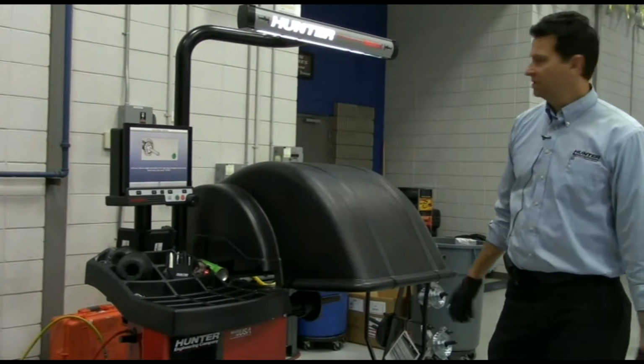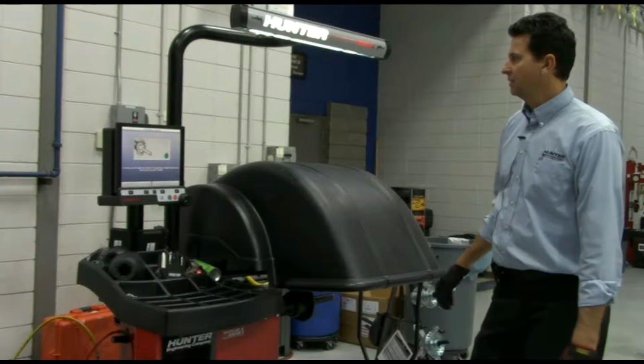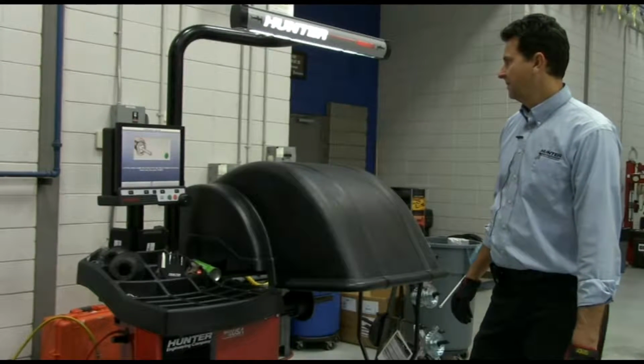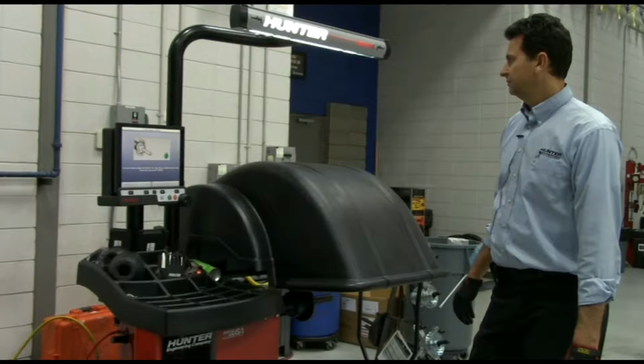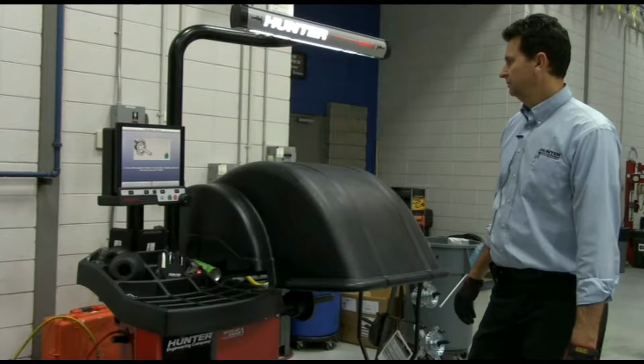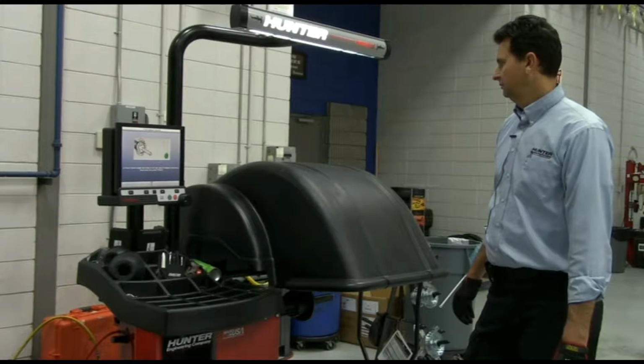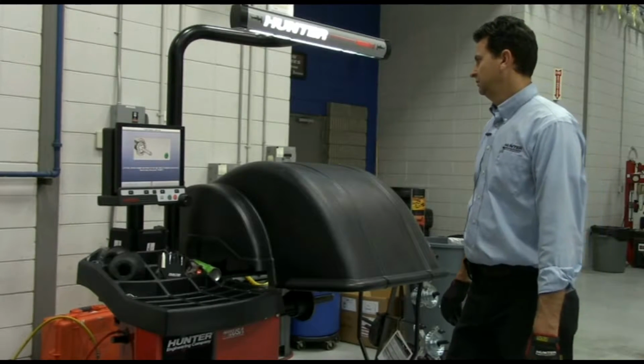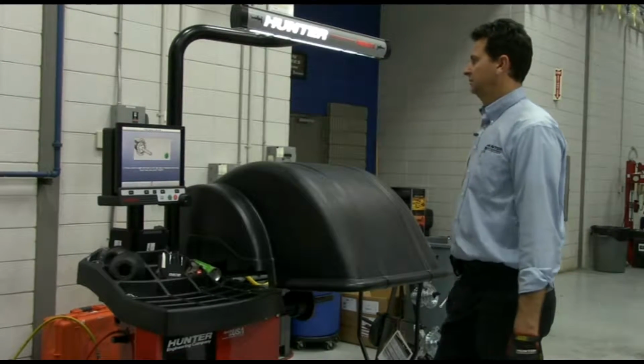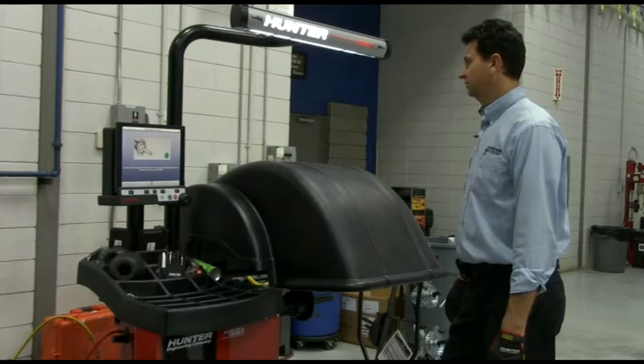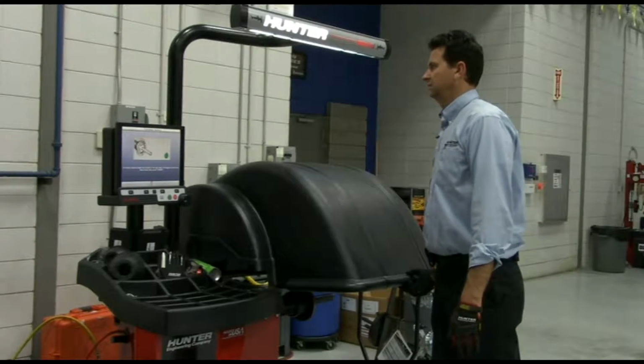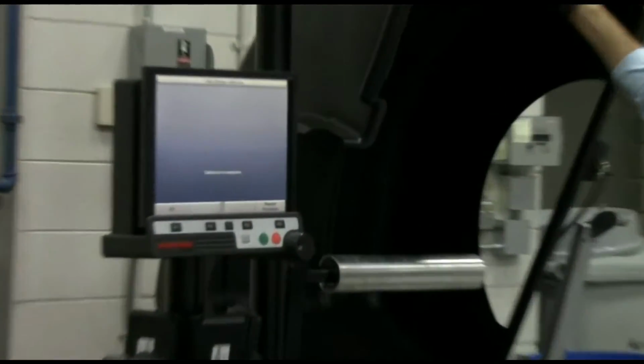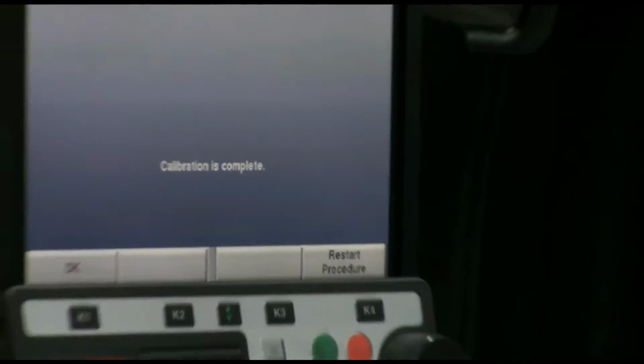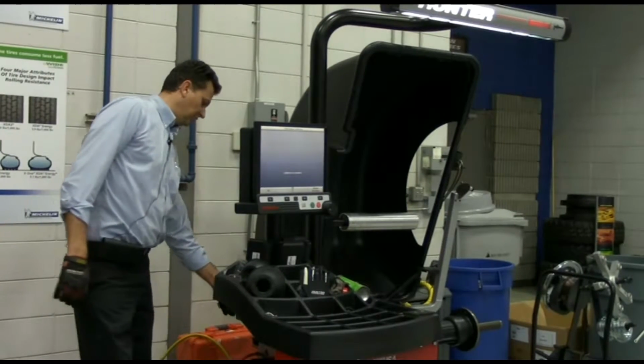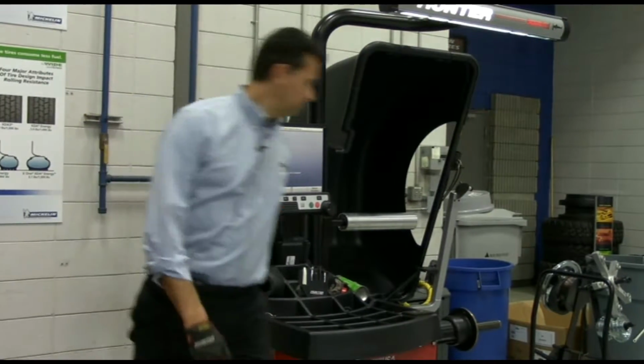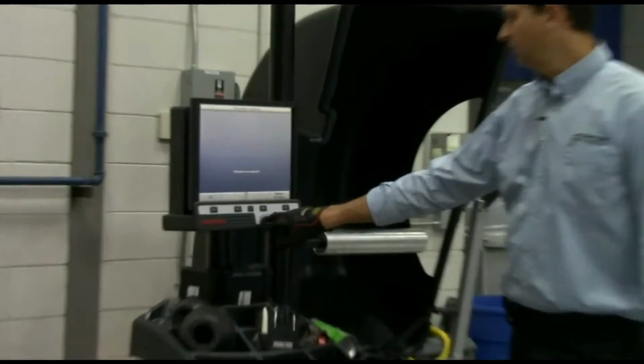This is the final step in the procedure. The third spin takes a little longer. It's about 20-25 seconds, and then we'll be calibrated. There we go. It says calibration is complete. So at that time we go ahead and pull our calibration slug out, and it just goes back in the threads on the back side of the machine. And we put that home, and then we can hit our reset key twice, go back home, and we'll be ready to balance.